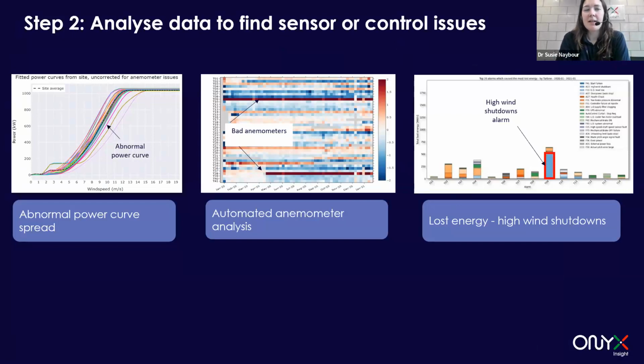Then the next thing to look at is whether that's actually an underperformance, or is it the sensor? We have an analysis in the middle showing the results—red means the sensor is reading higher than expected, and blue means it's reading lower than expected. We used a method to get what we predict it should be versus what it actually is, and then we can identify: in these cases, the red bars are two turbines where the anemometer is miscalibrated.